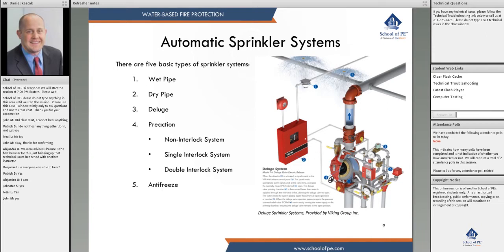The single interlock admits water to the sprinkler piping upon operation of the detector, so only one thing needs to happen for water to enter. A double interlock admits water when both the detection system activates and the sprinkler fuses — two separate actions required. A non-interlock admits water upon operation of either the detector or the sprinkler.